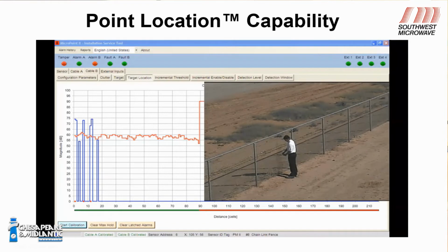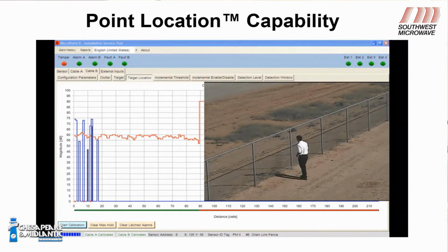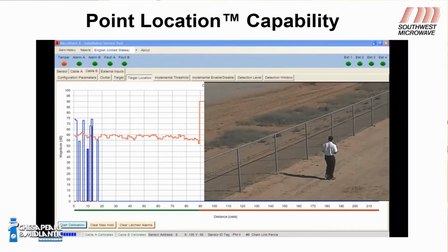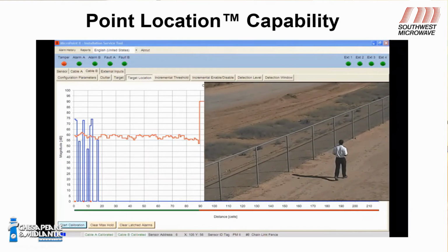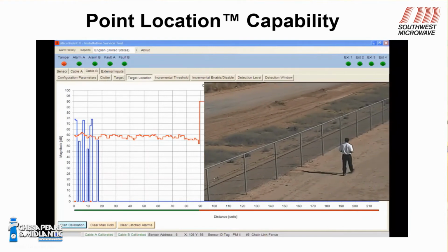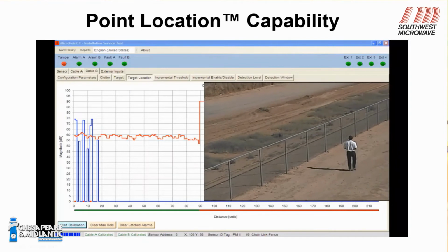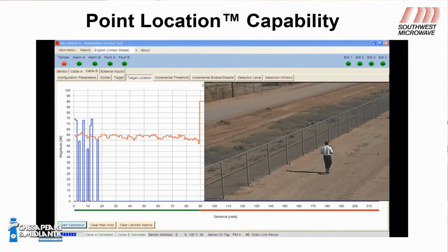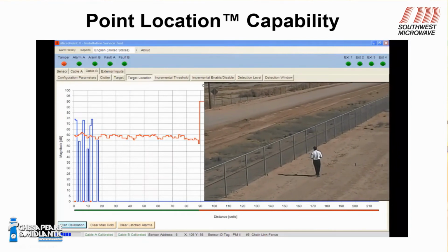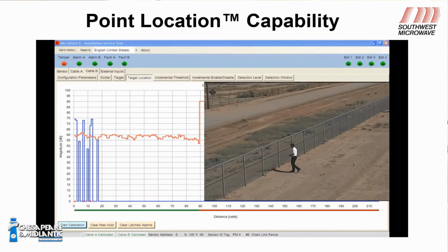What we want to do with this during the system installation is bring that sensitivity all the way down. We do like a -20. So we bring it 20 dB lower than the calibration. And then we use that cut simulation tool to ping the fence. And it gives us a response. And this tells us if I were to cut the fence with an average size bolt cutter, this is what the response is going to look like.